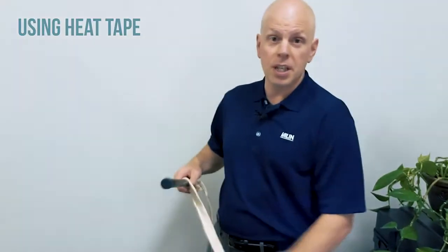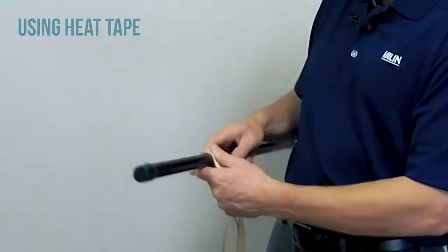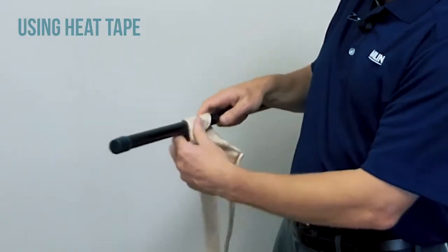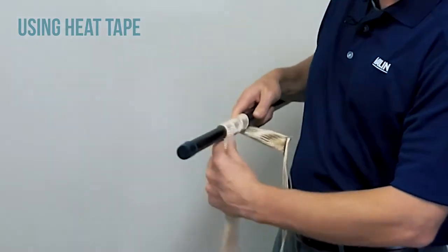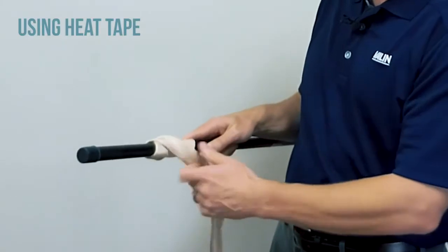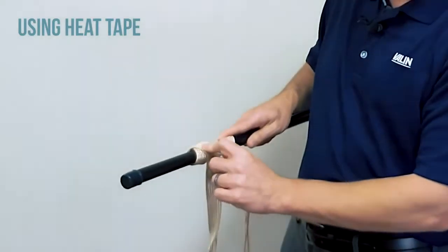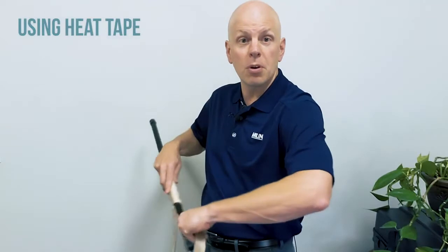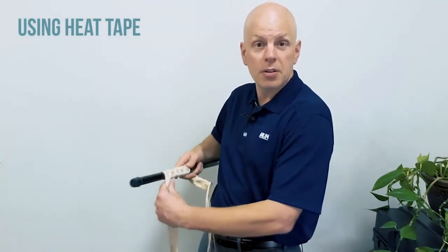Typically, when you're using heat tape, you want as much thermal energy as possible to go into the process. So you're going to tightly wrap the tape around the pipe. Please be careful not to overlap the tape, or you're going to get a hot spot right here, and that's going to cause a short circuit or a burnout. We always recommend using a control scheme on any heater system so that you have a feedback loop and can more effectively maintain the system at your desired temperature.